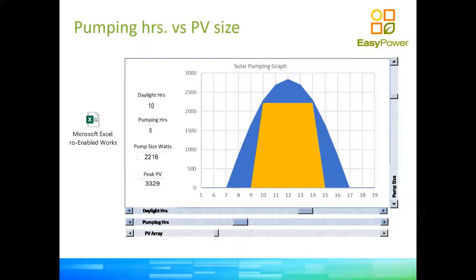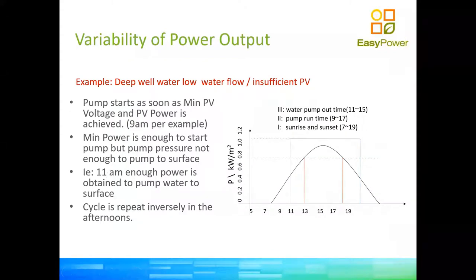Your pump inverter will behave better in summer — pumping for longer hours at maximum speed and producing more water — and conversely produce less water in winter. If you have a mission-critical application needing the same amount of water winter and summer, your design must be based on winter conditions so it performs well in winter and excellently in summer. The way to handle this is to over-panel the system, giving more hours of pumping in winter, and obviously much more water in summer.